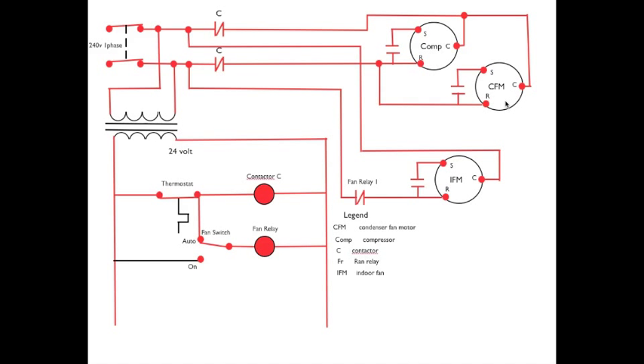Okay, at the same time power passes from the thermostat down here in 24 volt through the auto position, the fan switch, over to energize the fan relay.